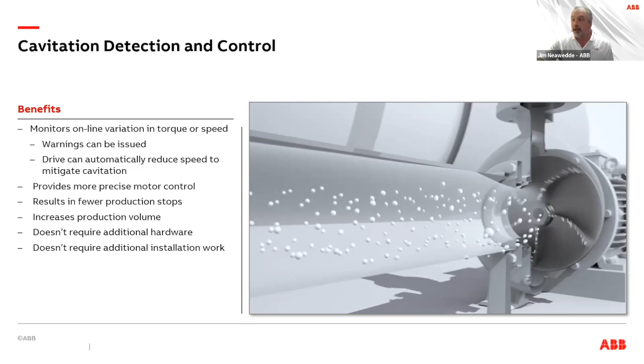This is very good when it comes to dairy. You're not changing the consistency of the product. Like when you take it out of the truck and you're pumping it into your plant, the level of the tanker goes down and the pressure goes down as well. And this will help compensate for that. And it doesn't require any additional hardware. This is all just done by the intelligence within the drive itself.